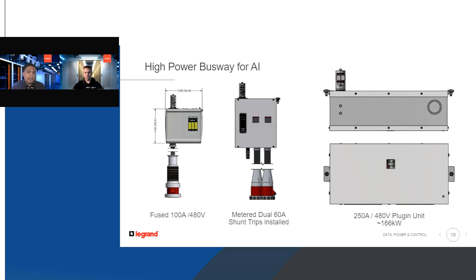Two other things worth noting: the unit on the left is a Fuse 100 amp solution. With this increasing AI power demand, we're seeing higher available fault current at the busway, and we're currently deploying fuses to help satisfy that electrical infrastructure. These fuses have a withstand of around 200K, which is more than sufficient to handle some of these higher short circuit available faults we're seeing at the busway.